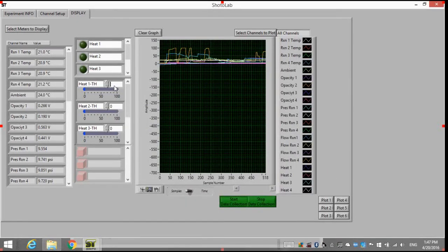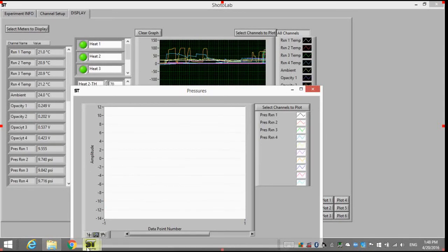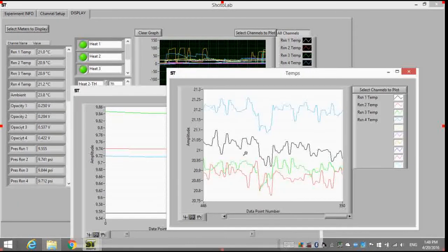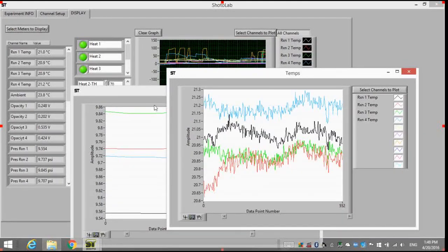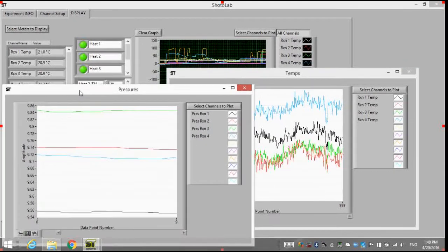Now let's set the PIDs to the temperatures we want. The first one's going to be at 60 degrees, the second one at 70 degrees, the third one at 80, and the last one at 90 degrees. You can see that the heat lights are indicating on now, and it should be heating up. And I don't want to waste 4 hours of your time watching this, so I'm going to speed it up relatively quickly, and you'll be able to see how the ShotoLab system runs. I'll put some comments also on the screen as it runs so you can see what's going on.